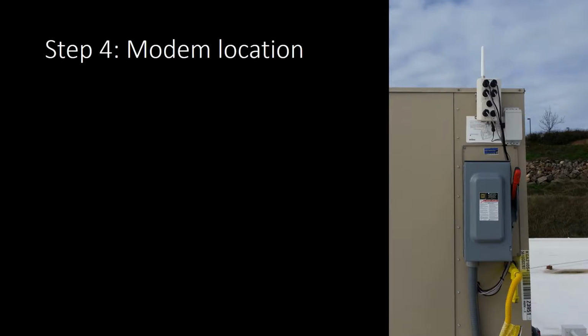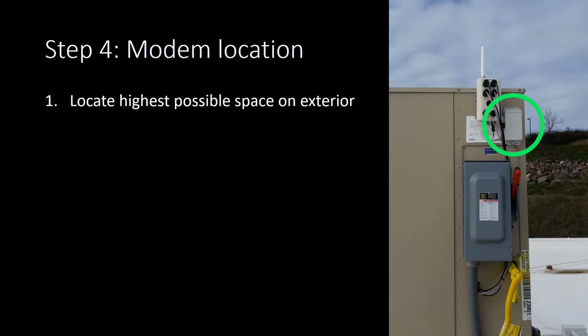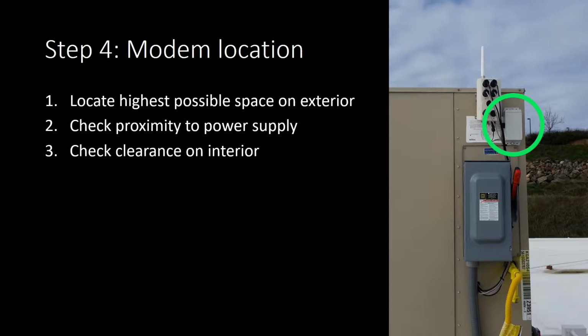Step 4. Determine a suitable location for the modem. Ideally, this will be close to both the location for the data collection unit and the power supply. Again, check for clearance and obstruction on the interior of the unit as we don't want sheet metal screws coming in contact with components inside the unit. Note, not every HVAC unit has a modem. One modem is installed in a central location for several units to share. Skip instructions for the modem if the HVAC unit you are working on does not require one.